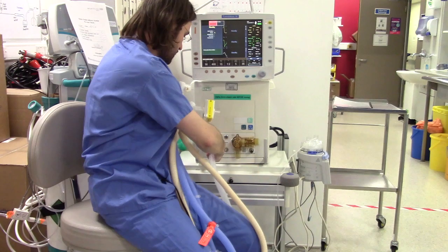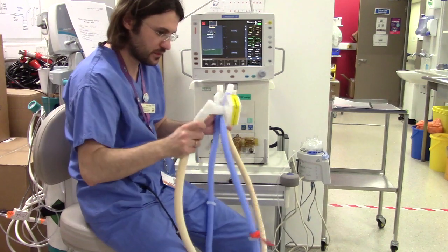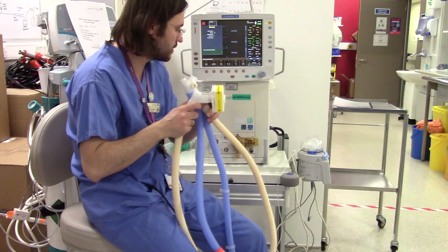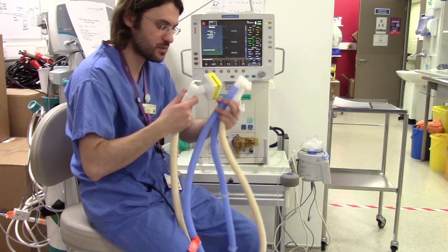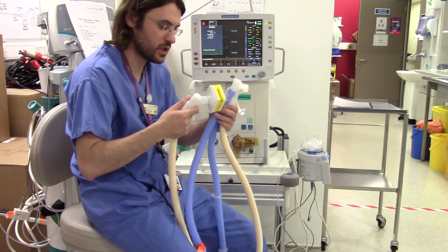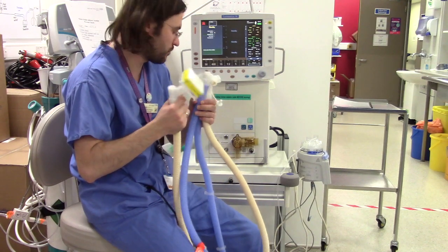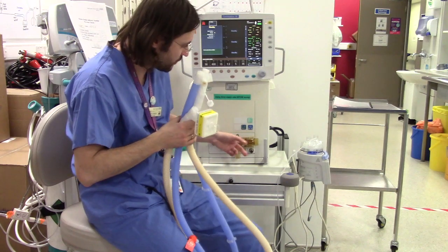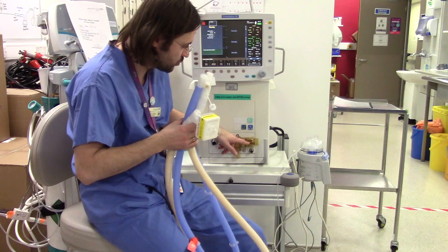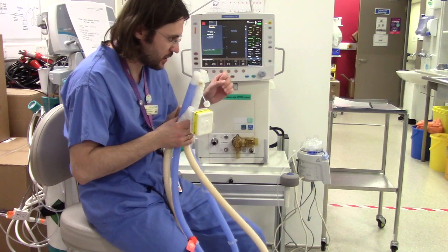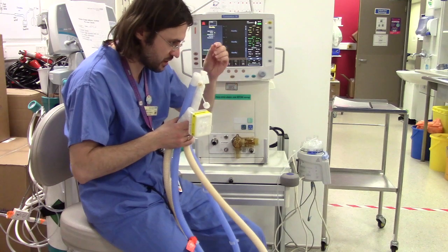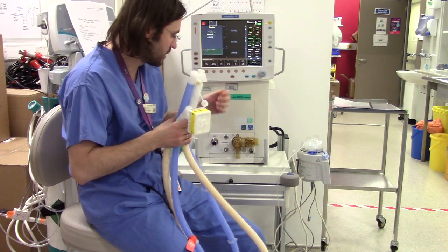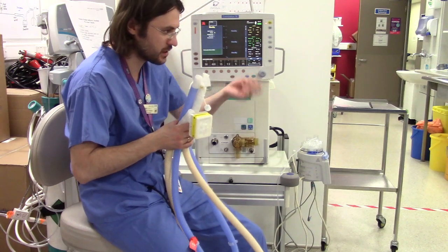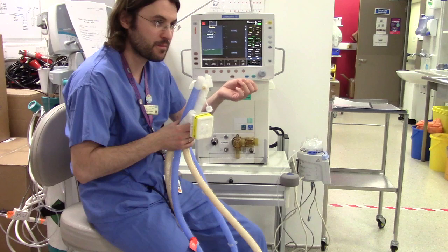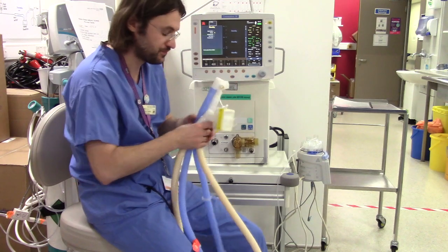Yeah, we don't use this. Remove it. Okay. You need a special antibacterial filter. This is a bigger one, and the reason why we're using it is that it stops the particles going through to the flow sensor, where they crystallize on the sensor and you get a false reading. That usually happens when you use a humidified circuit and some drugs that are delivered via the nebulizer. Yeah. So connect this bit over here.